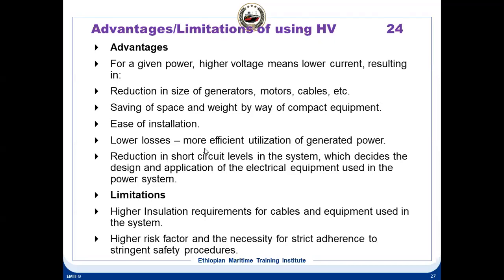Then copper losses are reduced, giving more efficient utilization of the generated power. The losses are reduced. Reduction in short circuit levels in the system is very important, because as the current is reduced, the short circuit current is reduced. Short circuit current levels decide the design and application of electrical equipment used in the power system. So your breaker capacities, your cable size, everything is reduced. These are the various advantages of using high voltage.